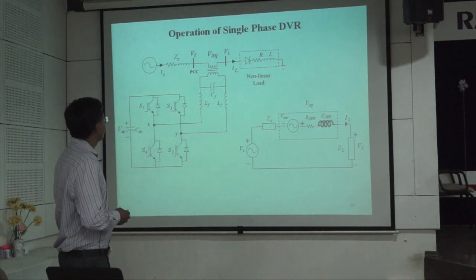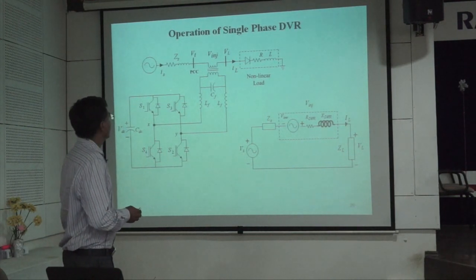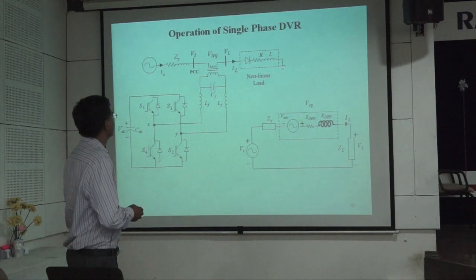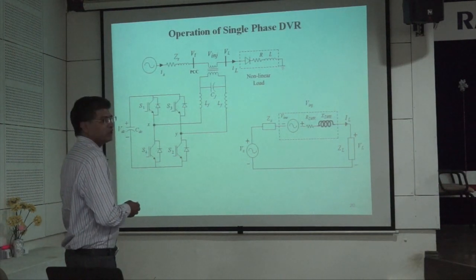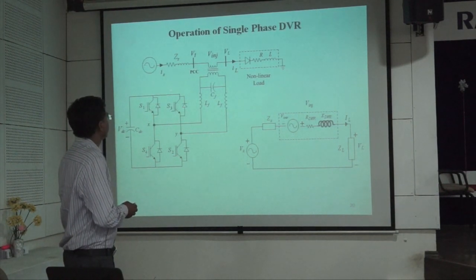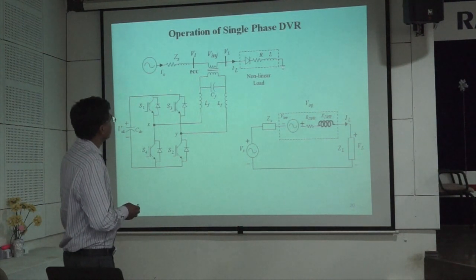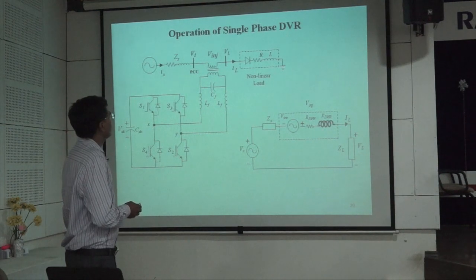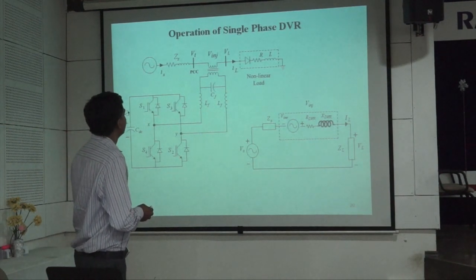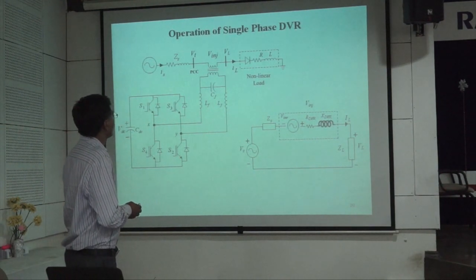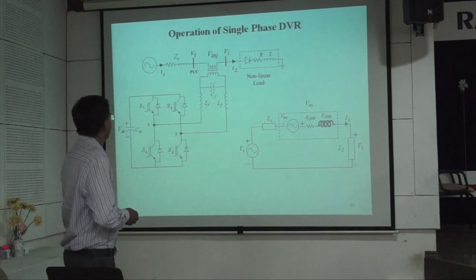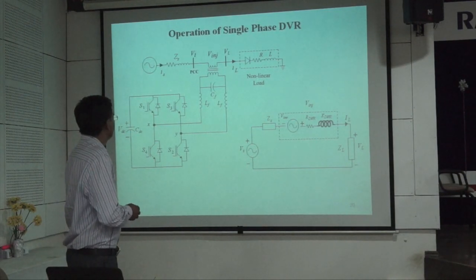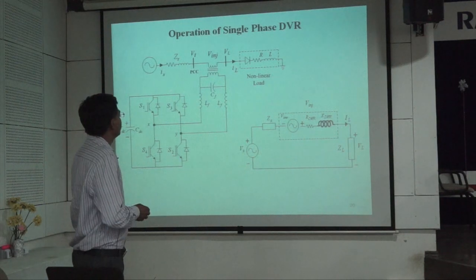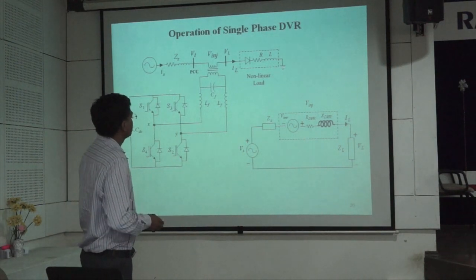How does it operate? Whenever there is a fault at another node, not shown here, there is a voltage drop in the PCC voltage, the VT terminal voltage. This affects the load voltage, so I have to maintain the load voltage at a desired value. That's why I have to inject a particular voltage at a particular angle. This is the complete system which will control the voltage and angle injected into the system.